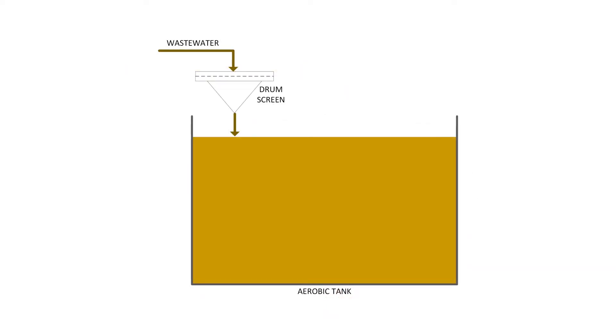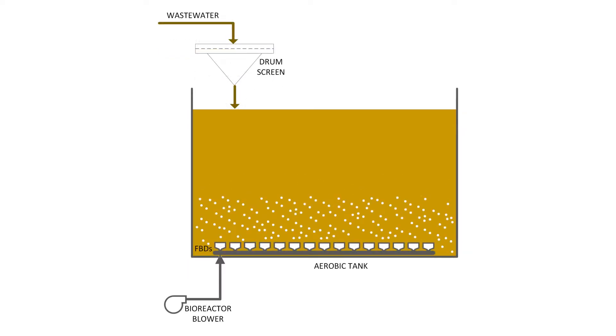From there, the pre-screened water gets introduced into a bioreactor where microorganisms decompose organic contents and achieve complete nitrification under controlled operating conditions. During this step, air is also introduced into the bioreactor tank through fine-bubble diffusers to provide oxygen required for biomass growth.